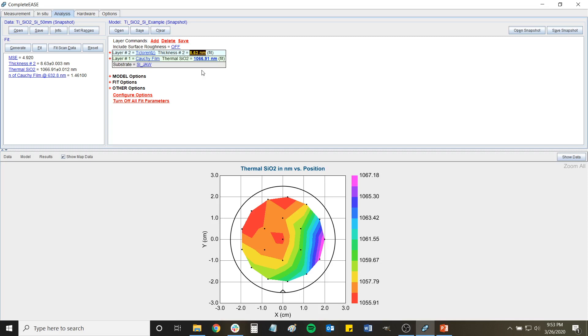Now the first thing you can do is you can say, hey, I wanted to put down 10 nanometers, let's say, and I'm getting something like 8.5. So it shows me that there's a little bit of an inaccuracy in the crystal rate monitor in my evaporator, so then I can adjust that with this information. The other thing it allows me to do is I could use this for something like an etch test.